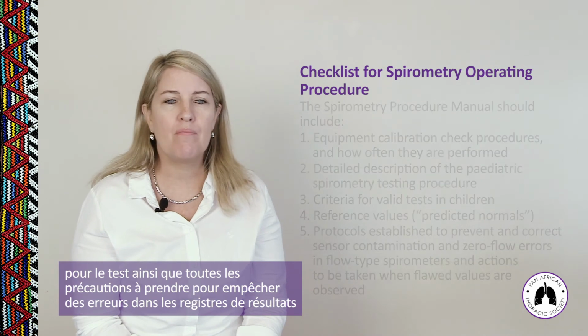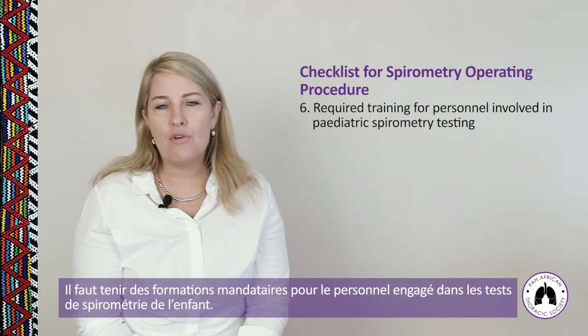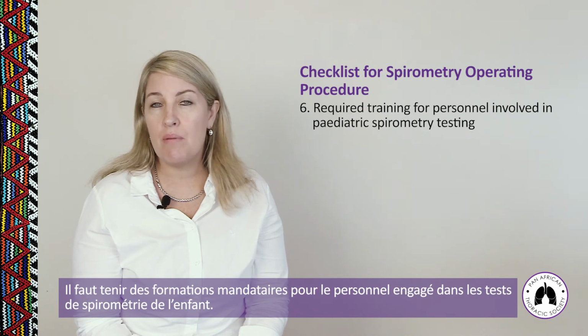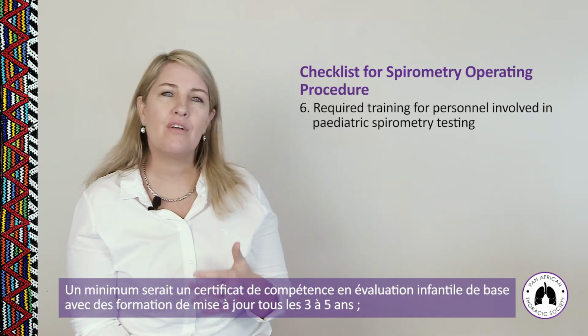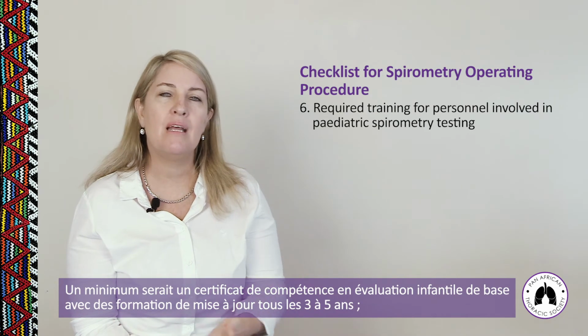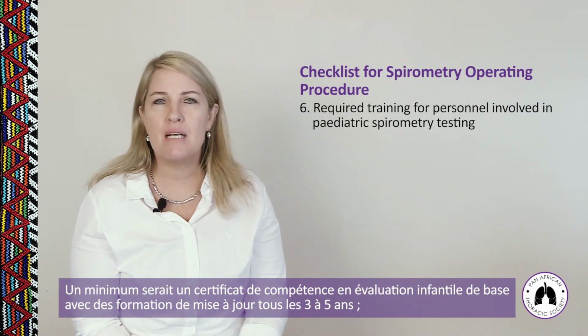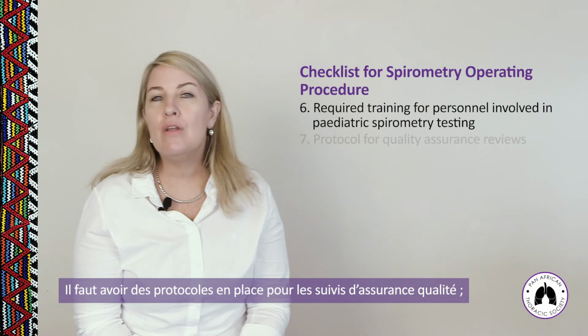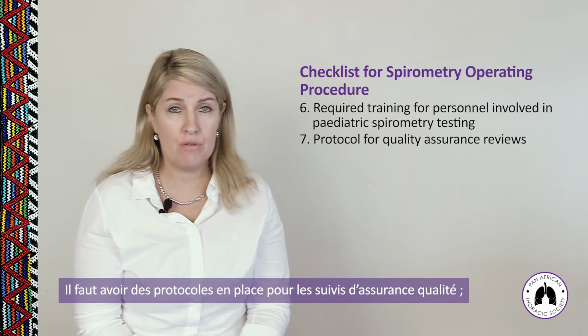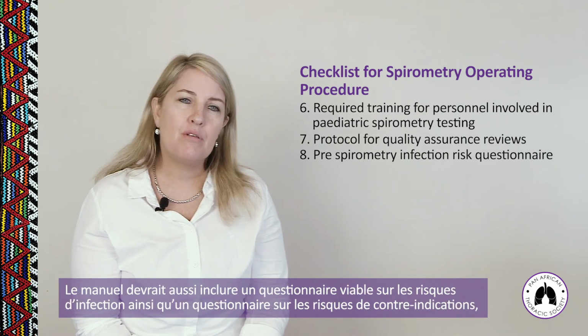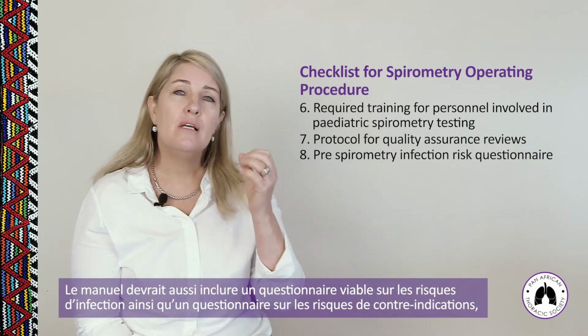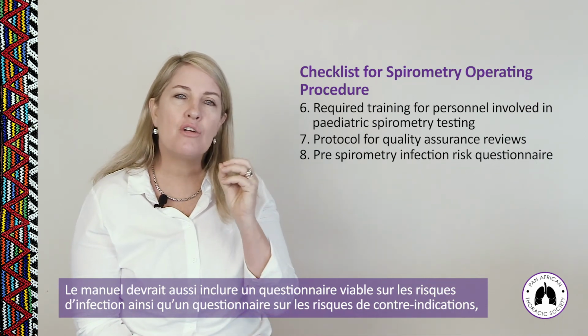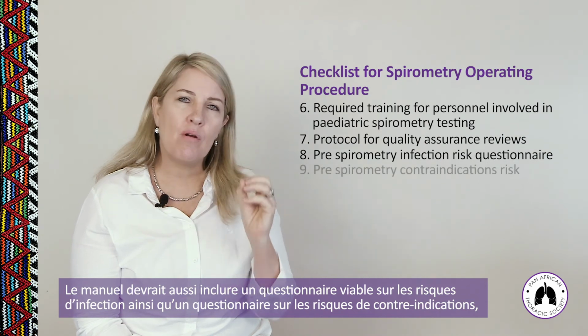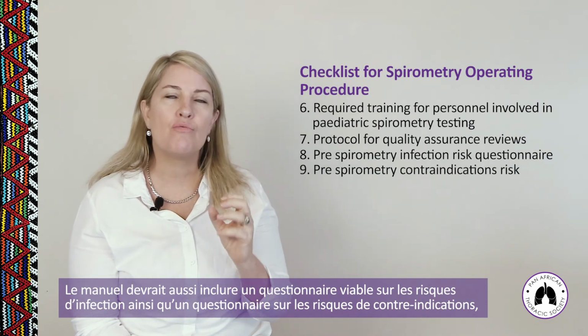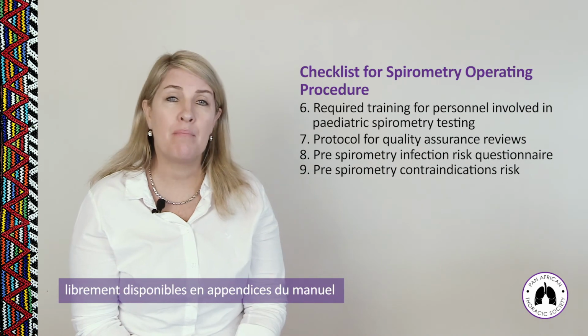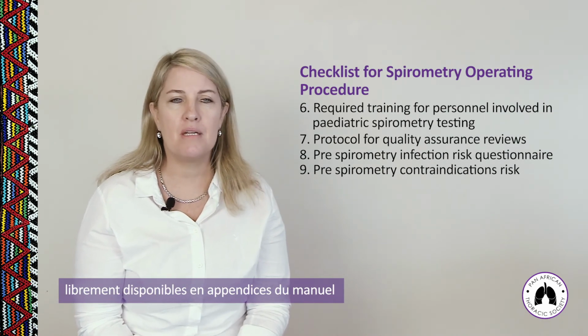You need required training for personnel involved in pediatric spirometry testing. The bare minimum is a certificate of competence in foundational pediatric testing with refresher updates every 3 to 5 years. You need a protocol for quality assurance reviews. The standard operating procedure should also include the spirometry infection risk questionnaire and the spirometry contraindications risk questionnaires readily available as appendices at the end of the document.